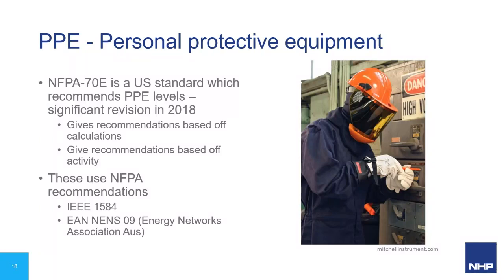That went through a significant revision in 2018. It seems to be updated every couple of years. It gives recommendations based off calculations, and it also gives recommendations based off activity. So basically, if you're going in to work on X, it says this is the sort of PPE you should be using. That NFPA information is then used by IEEE and even locally our Energy Networks Association document. So a lot of people pull from this NFPA one.